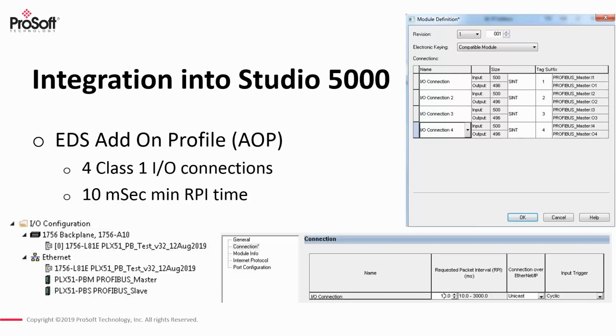Since the module utilizes EDS AOP for integration into the Studio 5000 environment, it does show up directly under the I/O tree and gives you status information, module information, allows you to utilize that just as if it's a native module in the architecture.